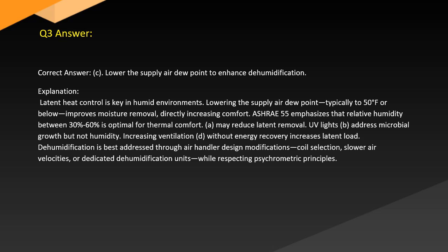Explanation. Latent heat control is key in humid environments. Lowering the supply air dew point, typically to 50 or below, improves moisture removal, directly increasing comfort. ASHRAE 55 emphasizes that relative humidity between 30% and 60% is optimal for thermal comfort. A. May reduce latent removal.